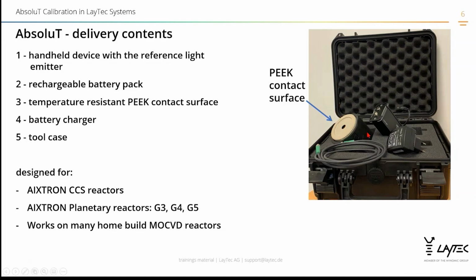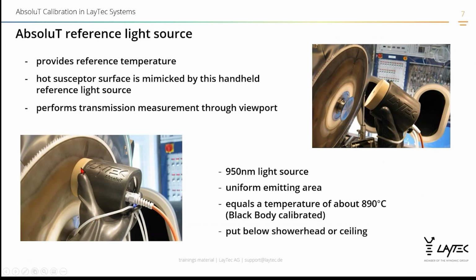So what it is, is an optical head. It's hand-sized. It comes with a battery, charger, and a cable between battery and optical device. And these parts need to be inside the open reactor lid. That is for all reactor machines where you can open the reactor lid and place the AbsoluT handheld set close to the ceiling hole or showerhead plane. And it mimics the spectroscopic part of Planck's thermal temperature spectrum in the wavelength range where we read the pyrometer signal.